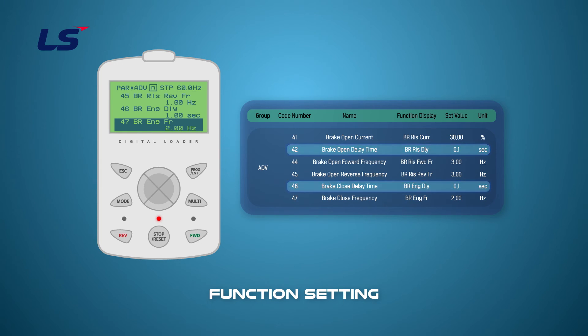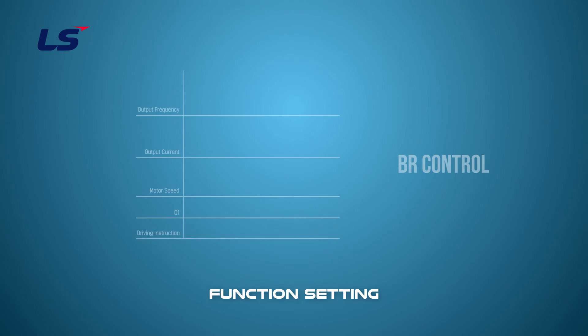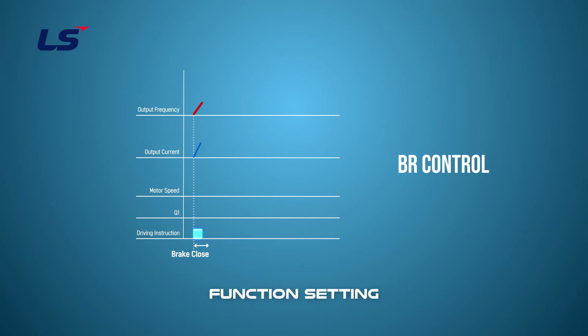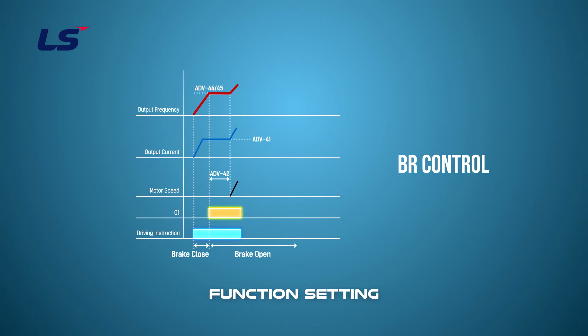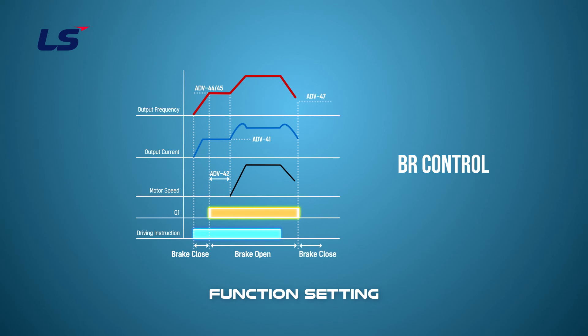Delay time parameters for brake open and close can be set according to the load characteristics. The BR control function opens the machine brakes by ON output signal when the motor reaches the open frequency and the output current reaches the set percent when the operation command is entered. When the closing frequency is reached after the operation command is off, the brake output terminals are turned off and the machine brakes are closed.